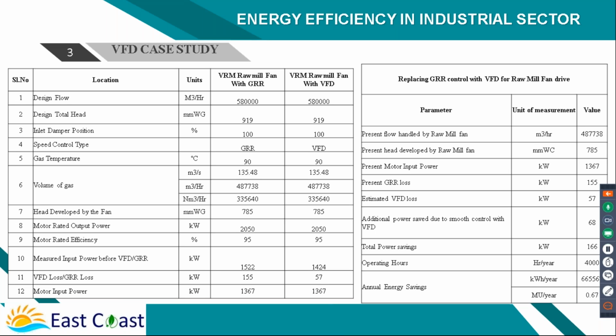The GRR itself is efficient since it also has a variable speed feature, but only in steps, not smooth control. And not only is it limited to steps, the resistance also consumes some power. Compared to that, the VFD saved about 166 kilowatt of power. So the point is, even if there is a controlling feature already, we can still study a bit deeper and see whether VFD fits in.